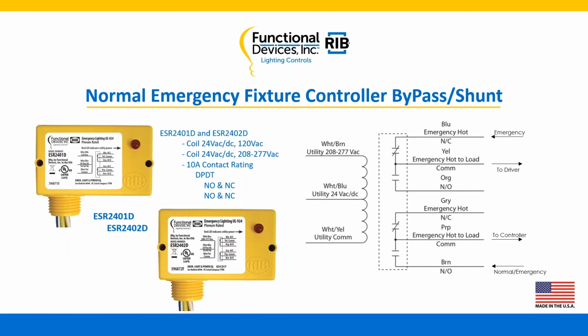Here you can actually see a normal emergency fixture controller bypass shunt. It's a little different application, and this is kind of key towards more of the distributed controls, so you're looking at the fixture controls and sensors at that point. Again, this is a double pole, double throw. What you're going to see is how you end up using one set of contacts. If you go to the bottom, you'll see the normal emergency power coming in. If this coil was activated, this would be closed here at this point, so we're feeding normal power around into the controller. When normal power drops, this coil deactivates. Then this opens up, and we're feeding the emergency power across this set of contacts, out to the driver to bring it to full brightness.